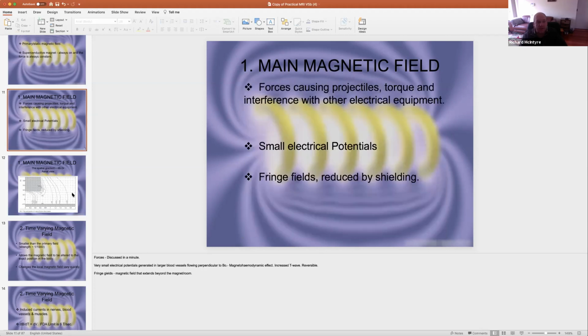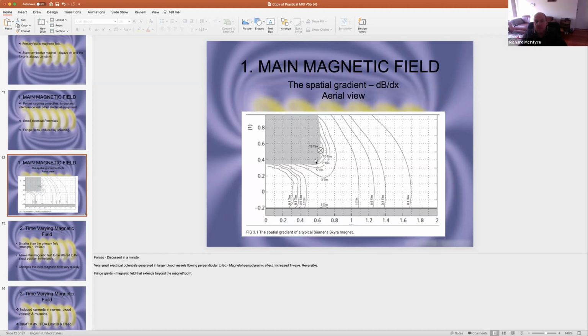So we've cut the top of the machine off horizontally, and we're looking from bird's eye, seeing just this corner of the room. And we know that this corner of the room is exactly the same as the front of the room, the other corner, and the 2 corners in the back. So all we have to do when we're looking at the spatial gradient is to look at one corner of the room. If we're looking from the roof, we've cut the front left corner out. We know that this is the isocenter. 0, 0 is the absolute isocenter of the machine. It's the middle of the machine, and as I said a little bit earlier, that isocenter is completely homogeneous.